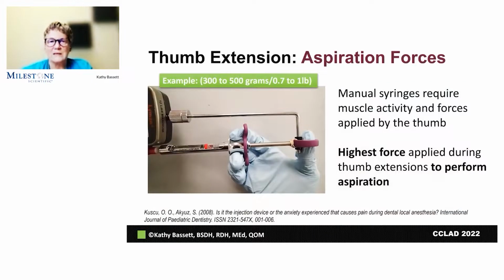One of the things that we did is we hooked up some syringes to a standard trigger pull gauge, and we measured how hard I had to pull to get that stopper to move at what I would call the average amount of pressure I need to aspirate. And we did that a number of times, and we measured both directions. How hard did I have to push?